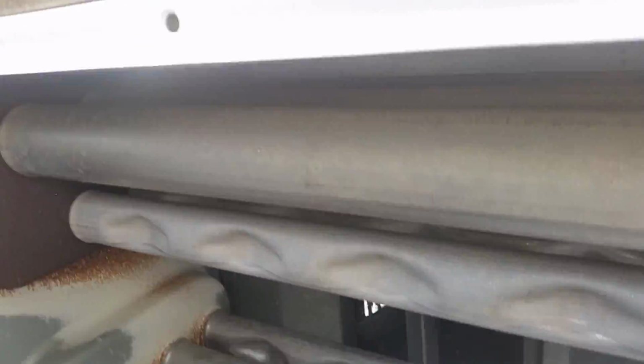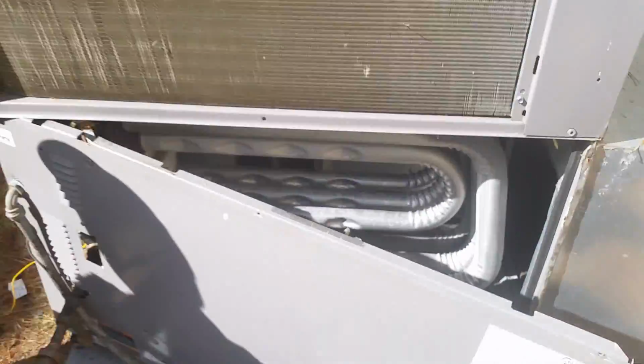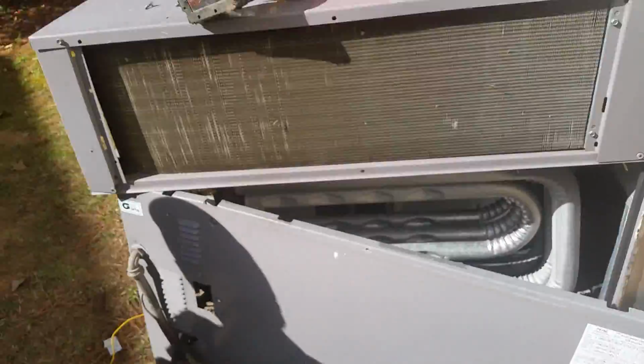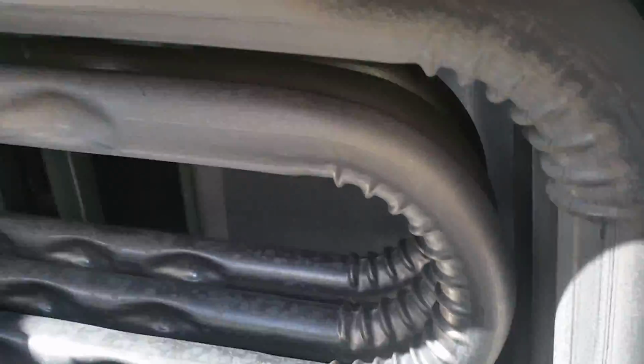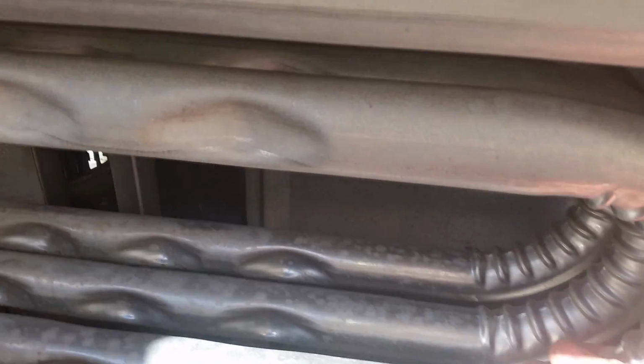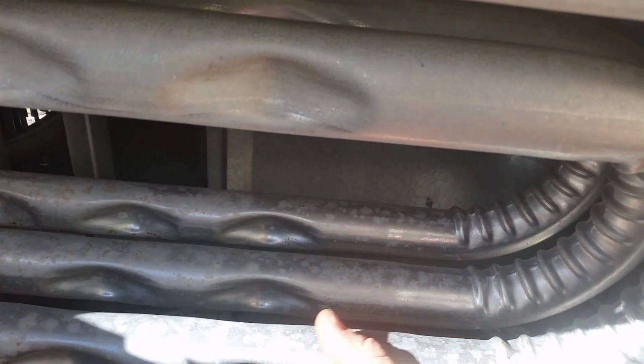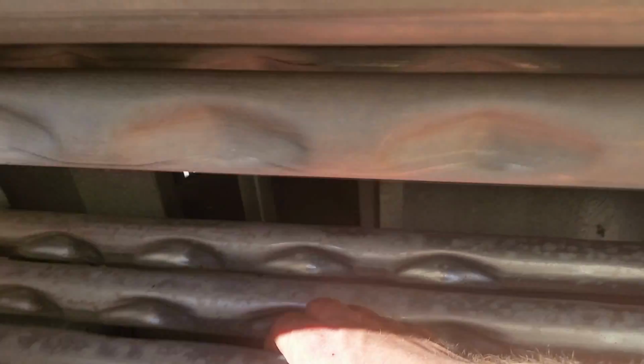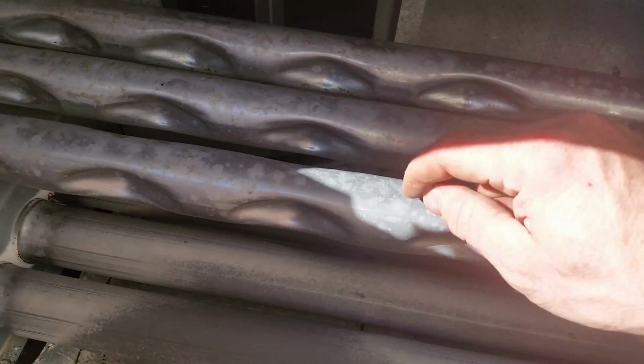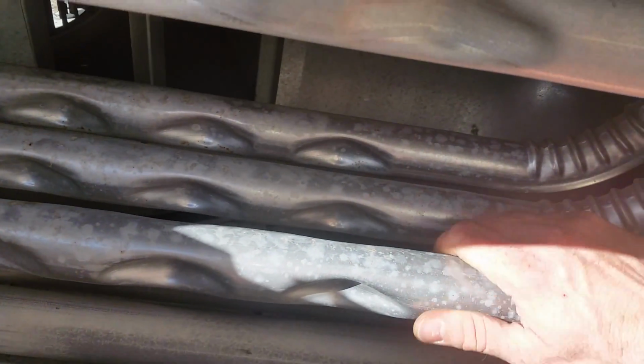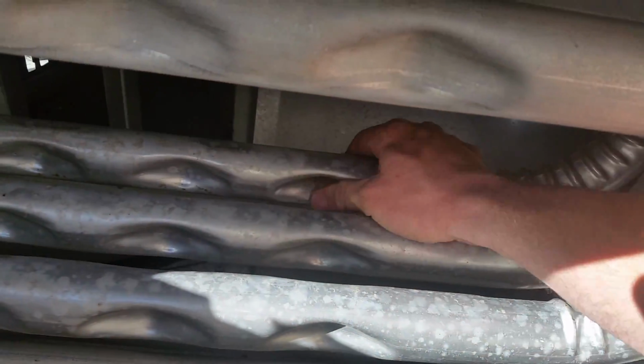Okay, so we've exposed our heat exchanger. You got to remove the side panel for that, and a lot of screws that you got to take off. But going through and physically with our hands, felt around each one of the pipes and being very careful to check every inch, every crevice, especially on the inside of these. On the other side, there'll be spots that they'll develop holes. So you got to be very thorough, feeling each and every pipe. And then if you feel a spot that's kind of extra rusty, take a little screwdriver or something, just kind of tap at it and see if it pushes through. If it does, then you got a hole.